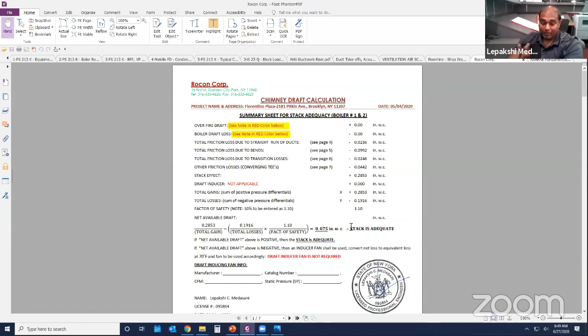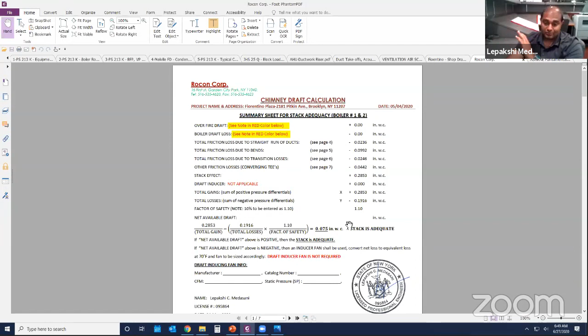And I'm going to just take, as a good rule in the design, you have to come up with some sort of factor of safety just in case. So I put 10% extra. So with the losses of 0.19 inches of water column, with 10% factor of safety, I get around 0.2 and something like that. So once you put positives and once you take the difference, you have 0.075 inches of water column of positive draft available at the exit of the stack, which means we have enough draft, which also means that whatever the exhaust gases that are being built up in the boiler can freely exhaust to the atmosphere.